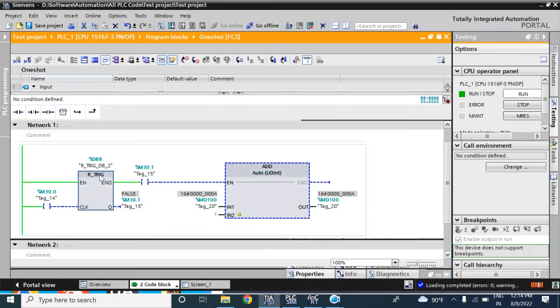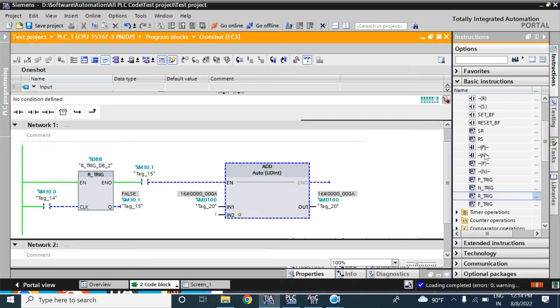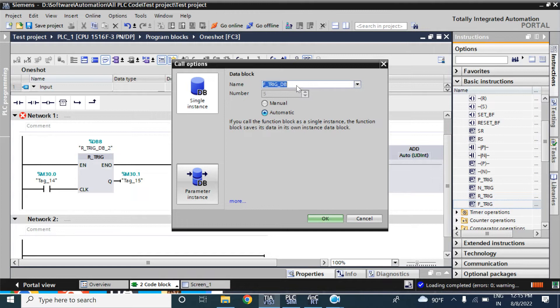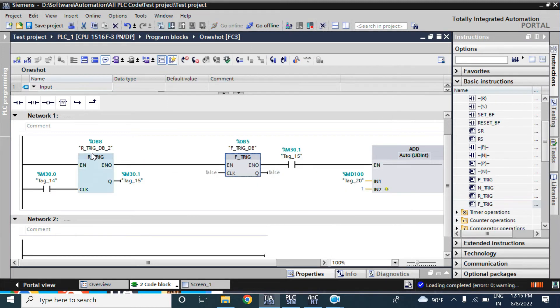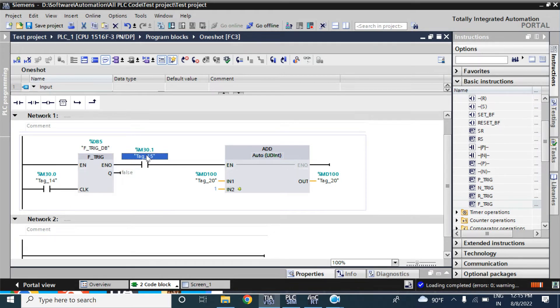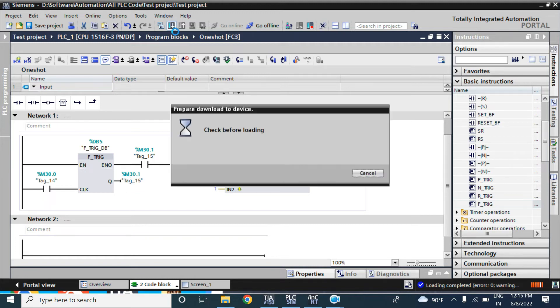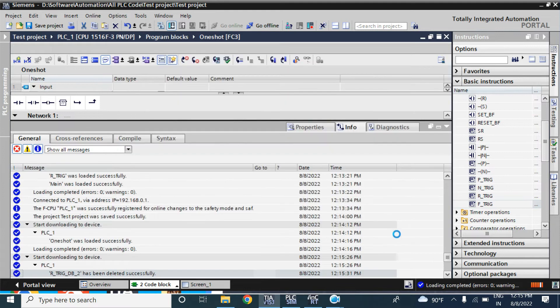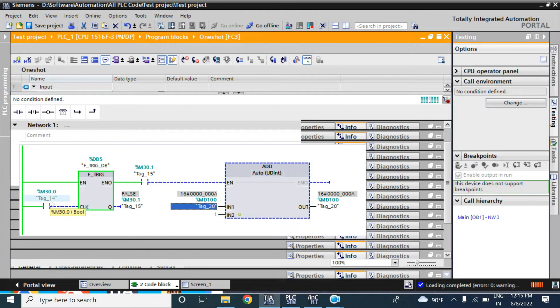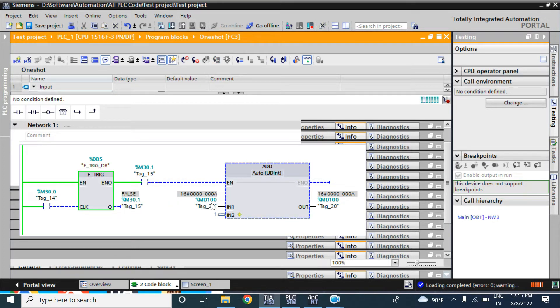Now I will use the F_TRIG. Here you cannot change R_TRIG to F_TRIG by just clicking and changing, as you can with other one-shot positive or negative bit logic. You have to add this function because the instance DB name here is not the same — that's why it requires a new add. I will delete this one and use this clock function here, and same as before I will use M here. So by this logic it will add once when the value of Tag 14 goes from high to low. When Tag 14 goes low from high, it will give an output for only one scan cycle and add one to MD100.